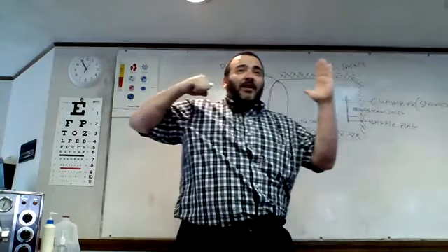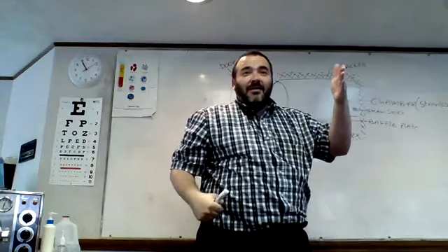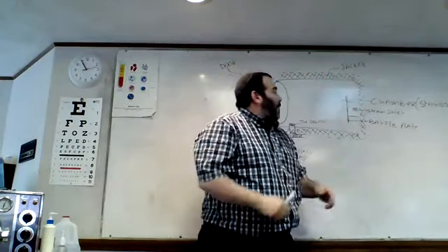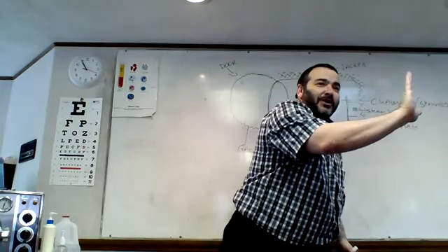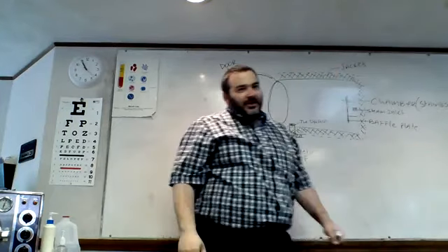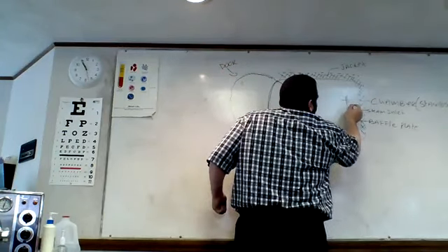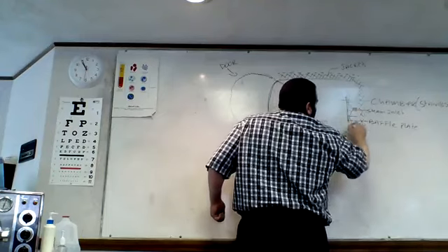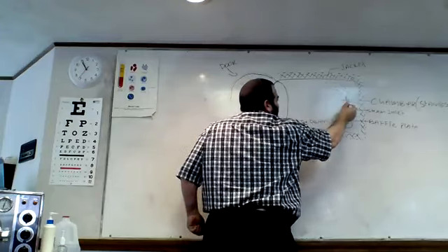So steam comes out at a high rate of speed. There's a baffle plate in front of it. It goes slam. Baffle. Whoa. So the baffle plate prevents the steam from shooting out directly into the chamber. But it hits it and it spreads out evenly throughout the entire chamber. You see that? So the steam shooting out this way really hard makes a sudden turn and spreads out in different places evenly rather than just shooting out this way.